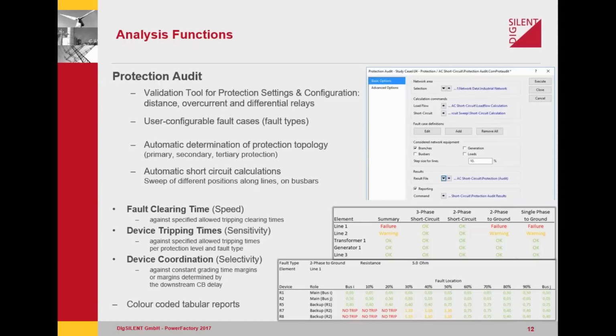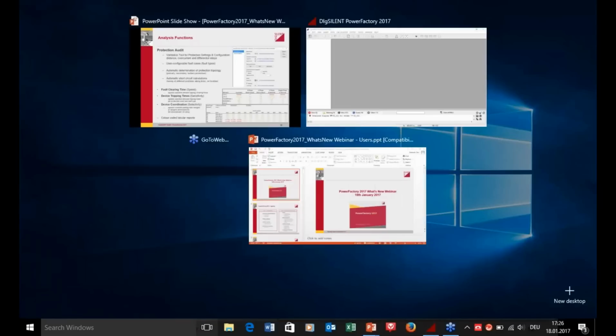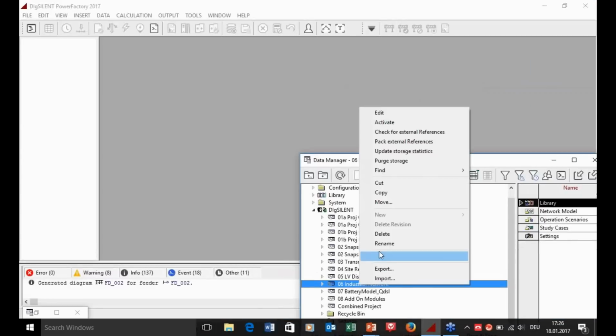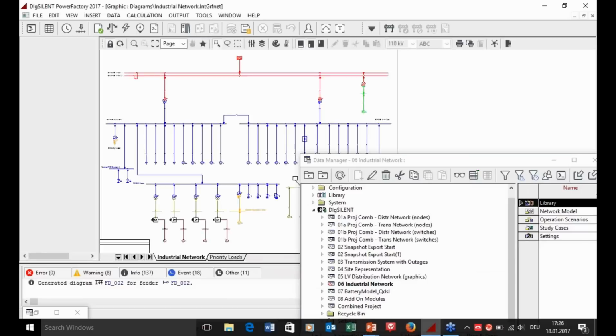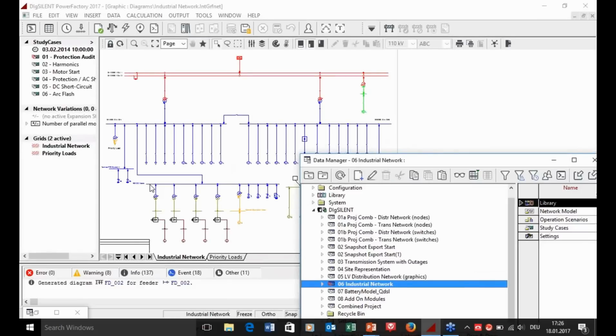The user specifies the network area to be examined, then configures the fault cases to be applied. The protection devices responsible for each network element are determined automatically according to the circuit breakers that they operate. In order to use the protection audit tool, the network model must include a protection scheme for which all the settings have already been defined.